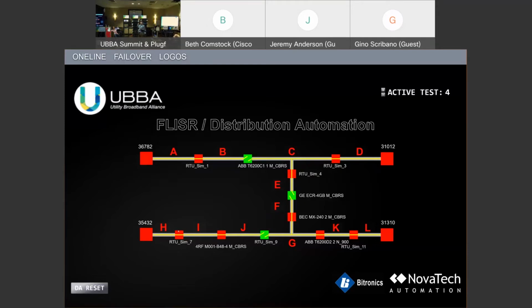Now two things can happen. The switch can fail to fully open, like the jaws get bound up and entangled, so it's just half open, at which point it stops, and that's a bad state to be in. So we stop everything and say we're not going to do anything else until we send a technician to deal with that switch.